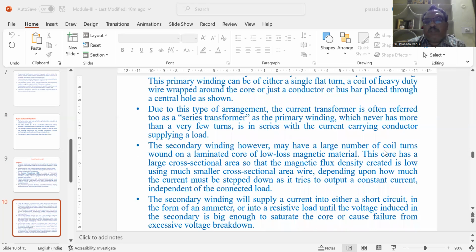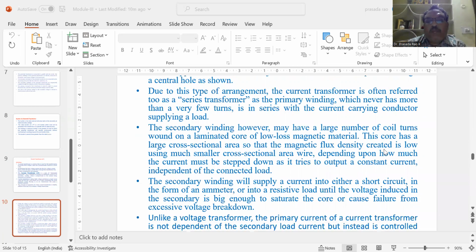The secondary winding will supply current into either a short circuit in the form of an ammeter or into a resistive load, until the voltage induced in the secondary is big enough to saturate the core or cause failure from excessive voltage breakdown.